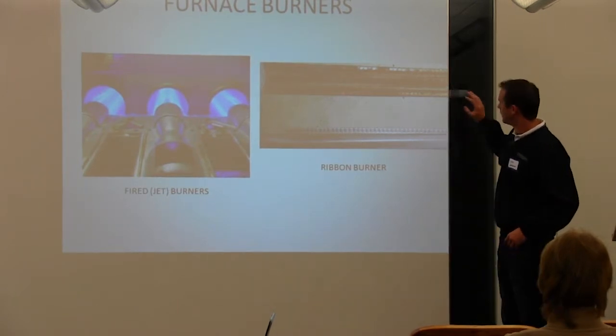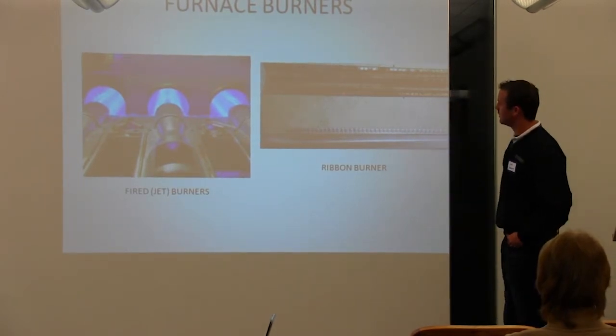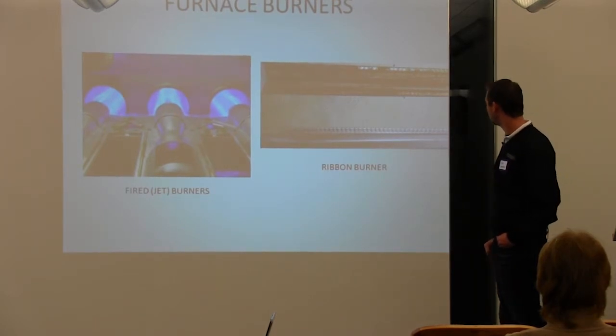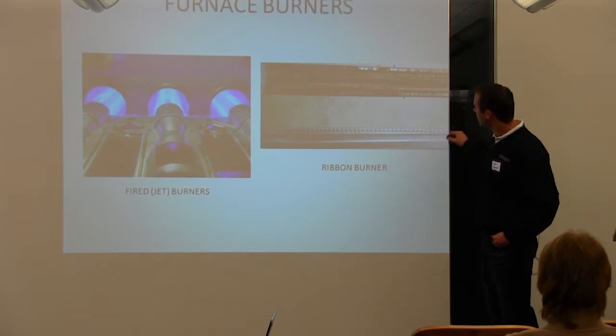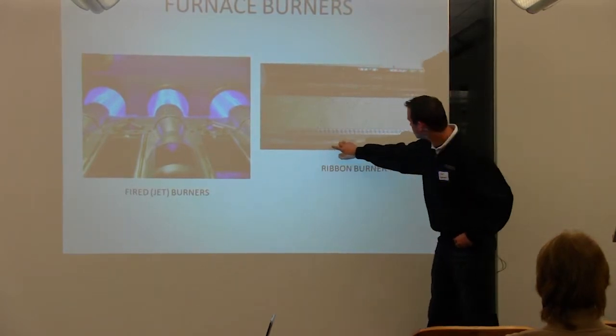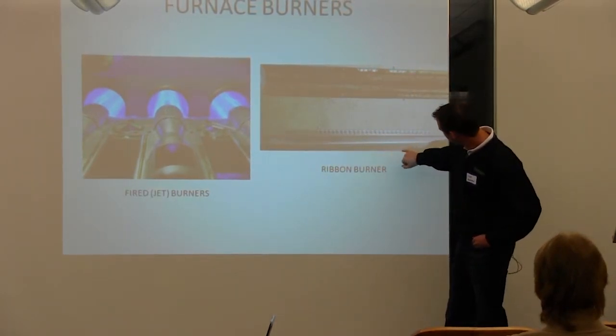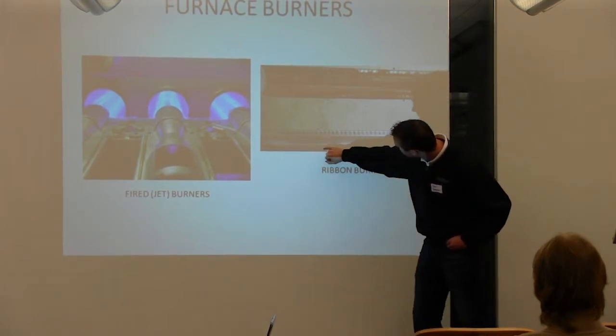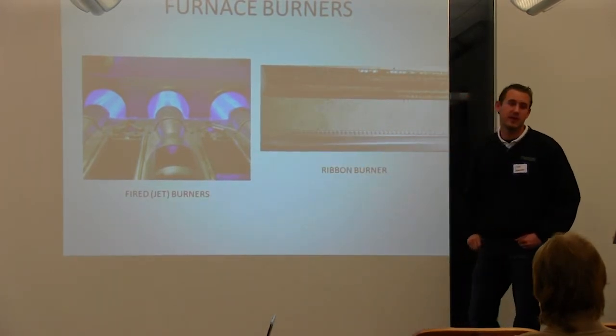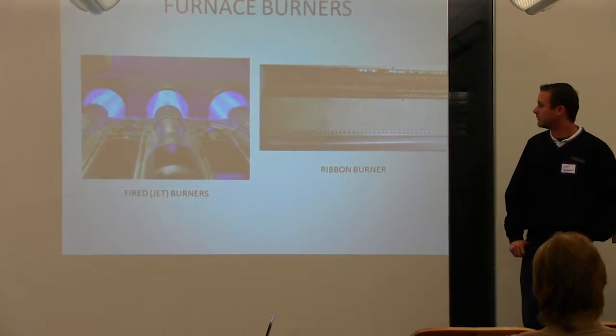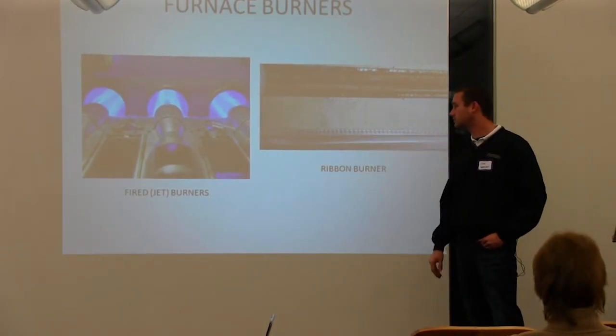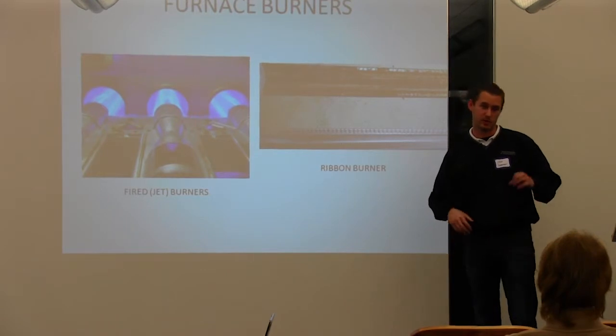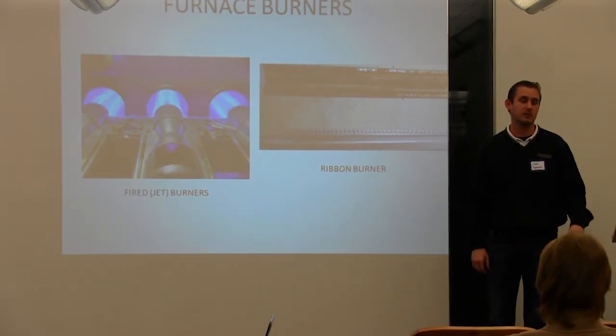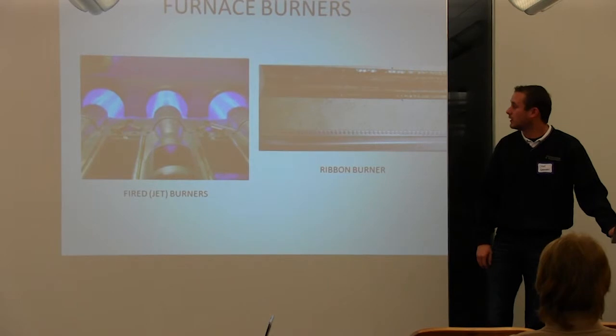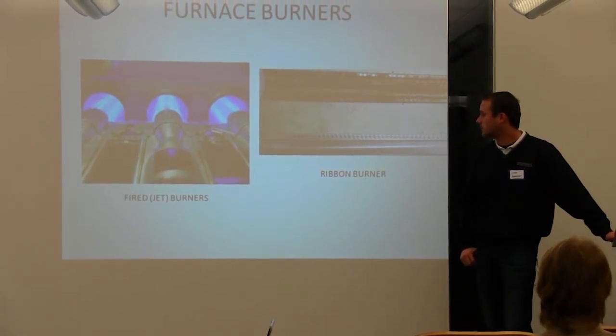The more common through the 80s and up to the 90s, and you still see a couple of them today, they're just not used quite as much, are the ribbon burners. And the gas gets shot through here, and you can see just very lightly all the little slits in there, and that's where the gas comes up and combusts. Now, the jet fired burners, those are pretty hard to gum up and clean. I mean, you're dealing with a hole about a couple of centimeters in diameter. And those generally are pretty maintenance-free.